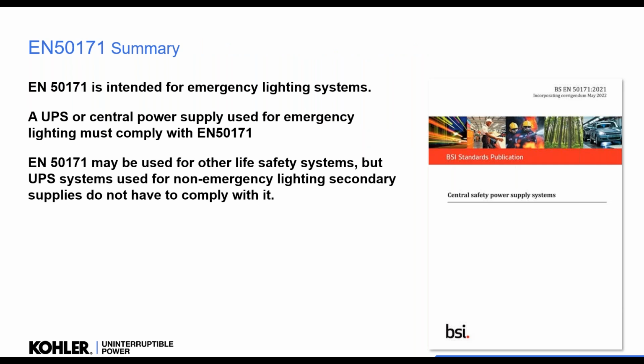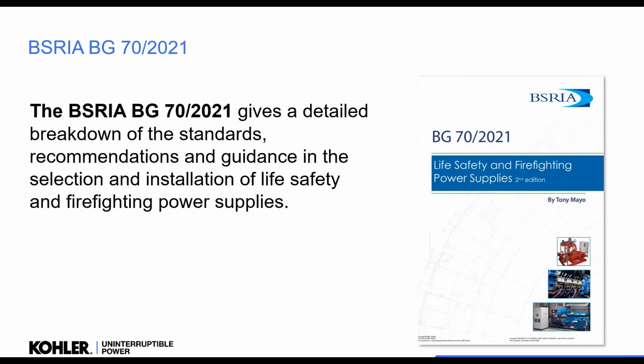It's a very good standard and has some very good recommendations that other regulations don't actually put in. So it does say you can use it, but if you're using it for a non-emergency lighting secondary supply, you don't necessarily have to comply with 50171. Okay, and if you want any further reading, the BSRIA BG 70 gives a very good breakdown of the standards around the selection, around life safety and things like that. So worth a look as well.